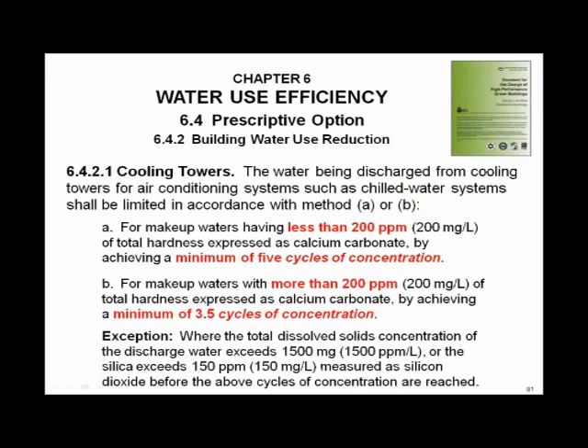ASHRAE 189.1, the so-called Green Building Code, the one the Army Corps of Engineers adopted, the one a lot of cities are adopting, and that you're going to see a lot more of, defines the cycles of concentration. It's the first time I've been able to find in ASHRAE any kind of code or standard recommendation on cycles of concentration. But here it is.